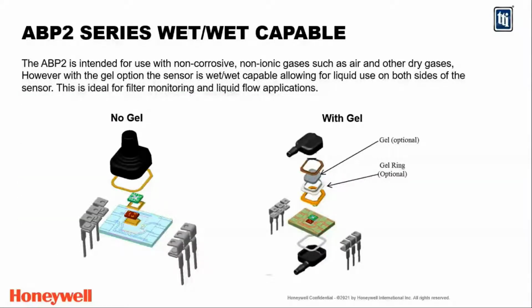We have an ABP2 wet capable, as I said. Our ABP and ABP2 series are both wet capable. How we do it is we have a gel ring, and we use that gel ring to contain the gel. So in other words, we fill the sensor after we've placed the die and ASIC and wire bonding and done all that type of work in the assembly. We put a gel ring down, and then we fill it with gel. And we could fill it with different types of gels for the application. We have a silicone, food grade silicone, as well as fluorosilicone available.